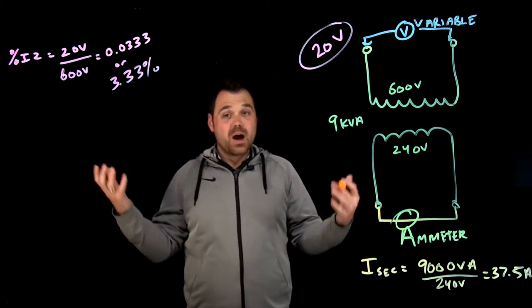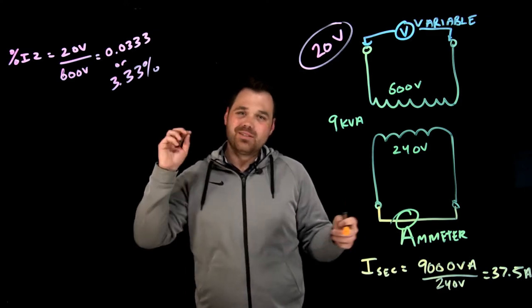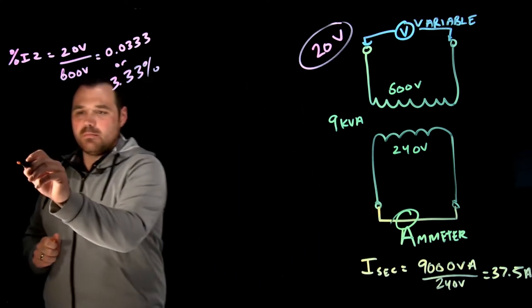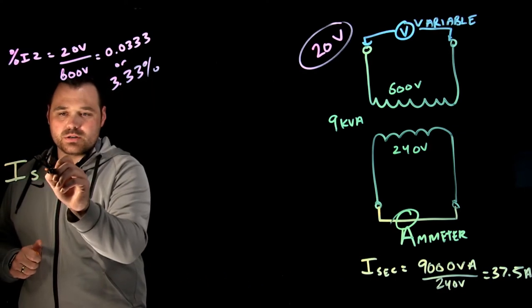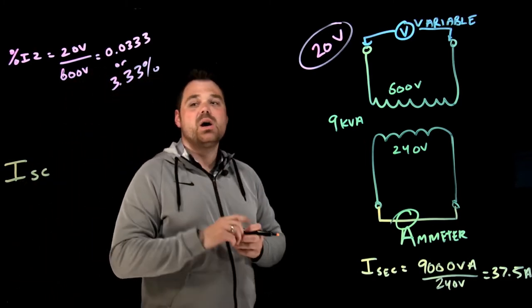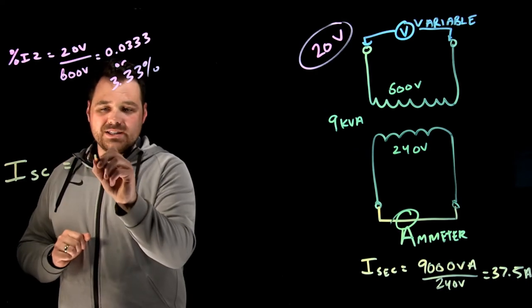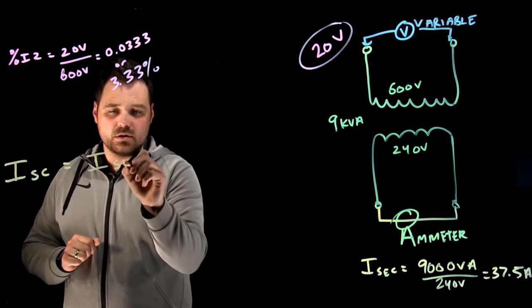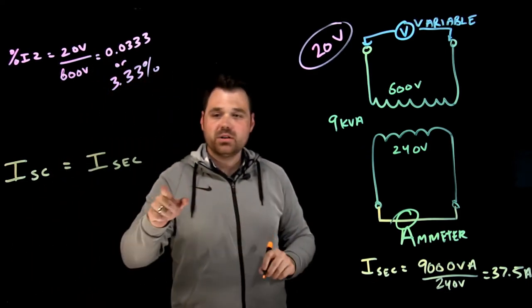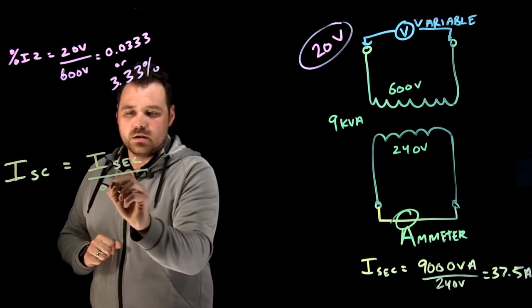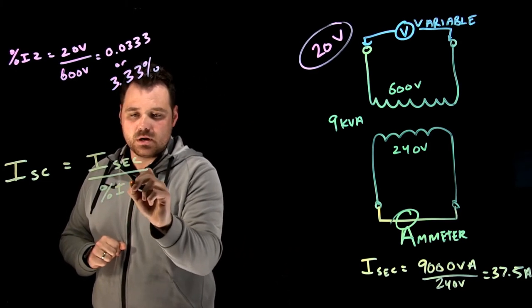Awesome. Now, what do I want to do with that number? Let's say I want to calculate my short circuit current. So what am I going to do? I'm going to take my rated secondary current, my rated current, and I'm going to divide it by my percent IZ.